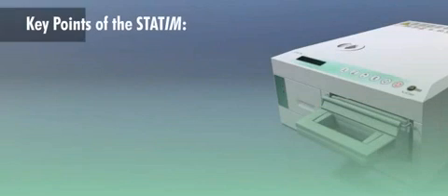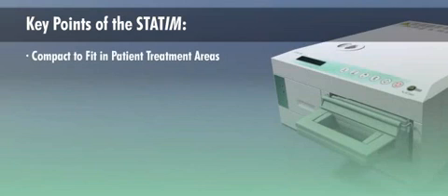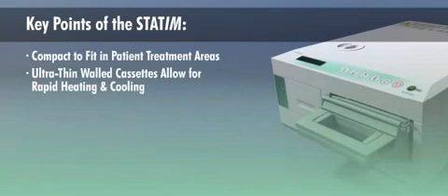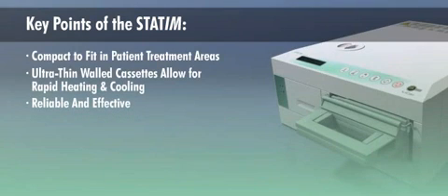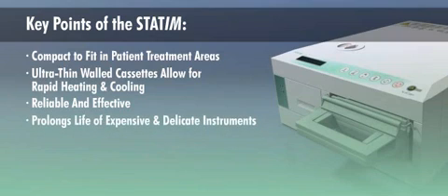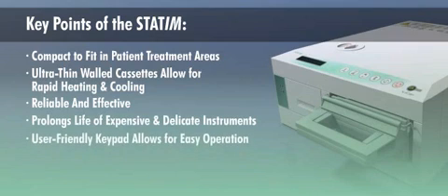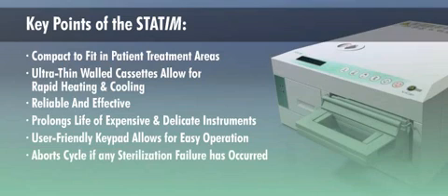Let's review the key points of the STATIM system. Its compact tabletop design conveniently fits in patient treatment areas. Ultra-thin-walled cassettes allow for rapid heating and cooling for fast in-between patient sterilization. Sterilization is reliable and effective, removing all of the air from the fine lumen of dental handpieces. Gentle sterilization prolongs the life of expensive and delicate instruments, keeping them rust and corrosion free. Simple, user-friendly keypad allows for easy operation. STATIM's fail-safe process evaluation system feature aborts the cycle if any failure of the machine to achieve sterilization conditions has occurred. Its self-diagnosing ability indicates problems on the electronic display.